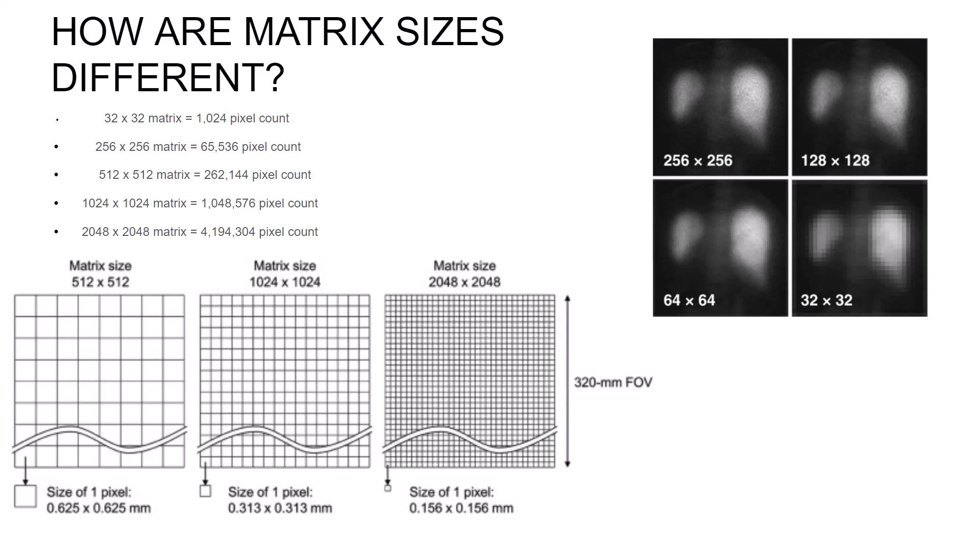And then you have 2048 by 2048, which is found in DR and digital fluoroscopic units with flat panel detectors. The important thing to note is the larger the matrix, the smaller the pixels, and the higher the resolution of the digital image.